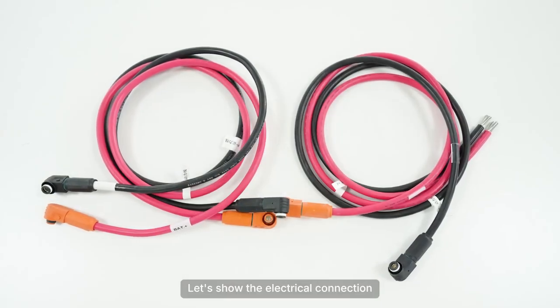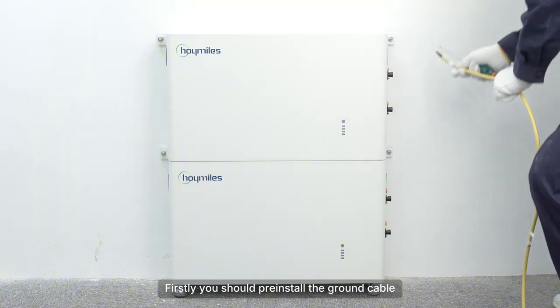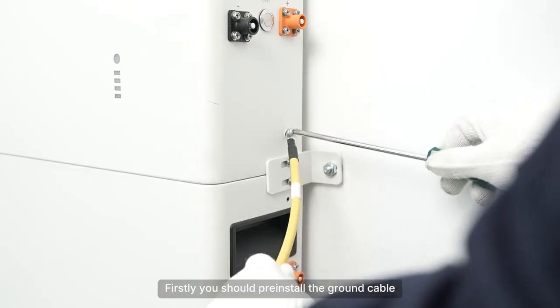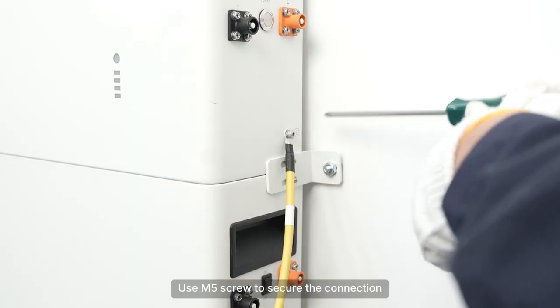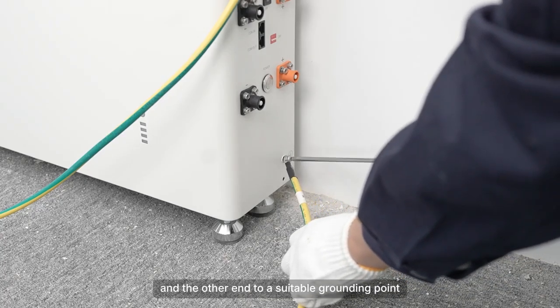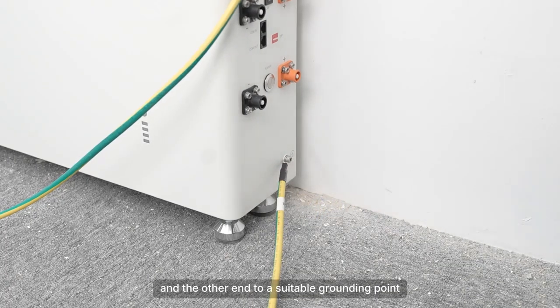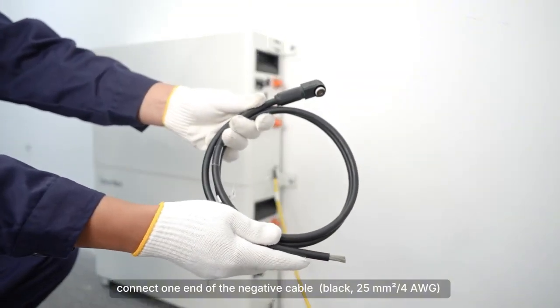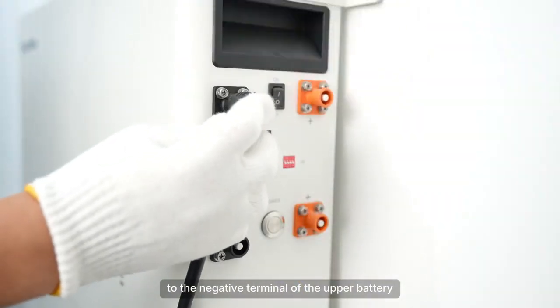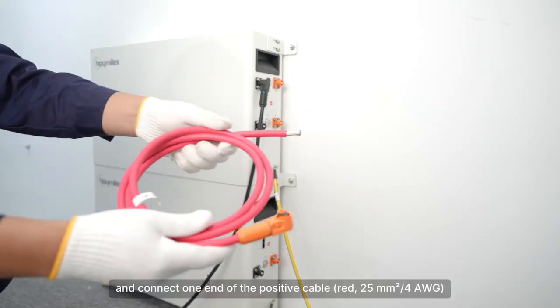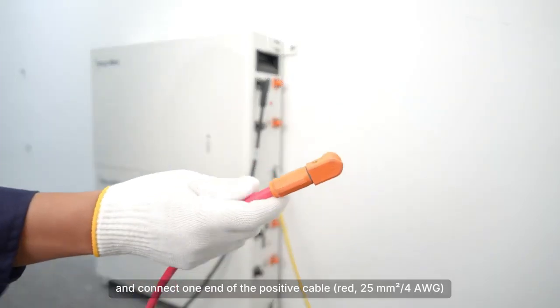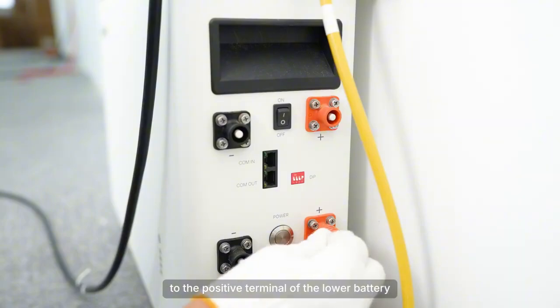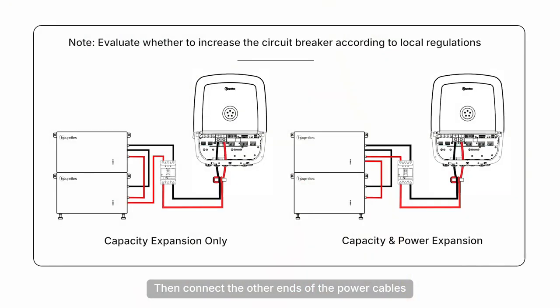Let's show the electrical connection for floor installation. Firstly, you should pre-install the ground cable. Use the M5 screw to secure the connection and the other end to a suitable grounding point. Connect one end of the negative cable to the negative terminal of the upper battery, and connect one end of the positive cable to the positive terminal of the lower battery. Then, connect the other ends of the power cables to the corresponding terminals of the HIT.